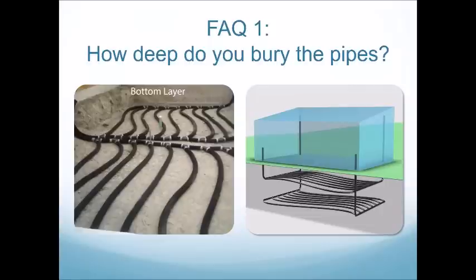Ideally, we'd go down about 12 feet to get that truly consistent earth temperature, but due to typical foundation depths for greenhouses and the economics of excavation, four feet is a sufficient and high-performing level. Soil temperatures vary depending on where you are, which is a factor we take into account when designing GAHT systems.